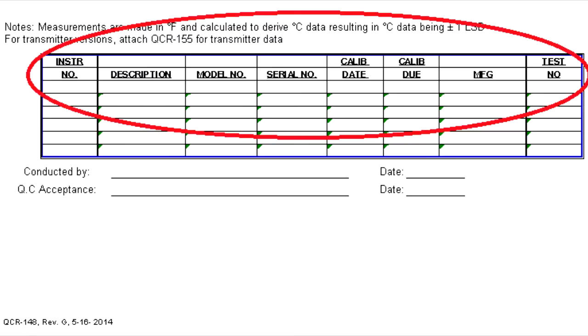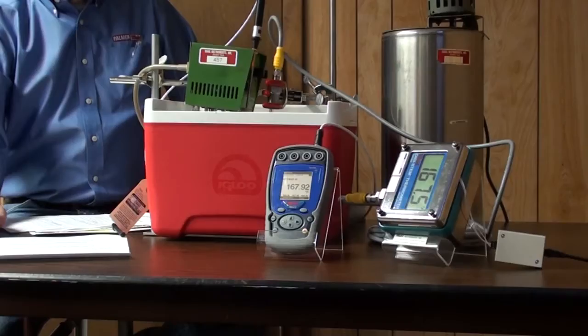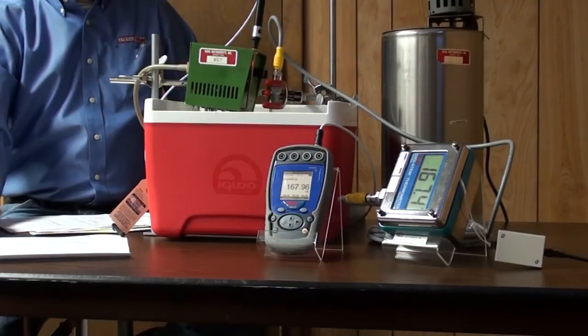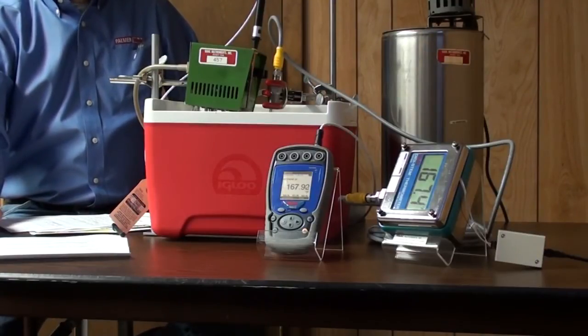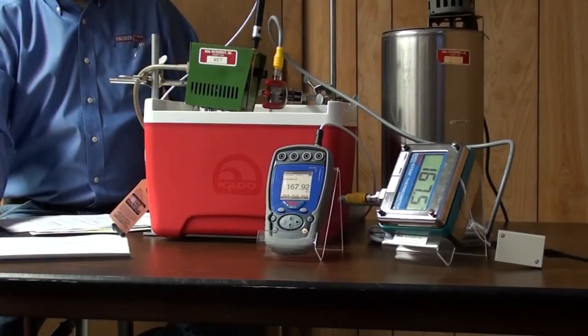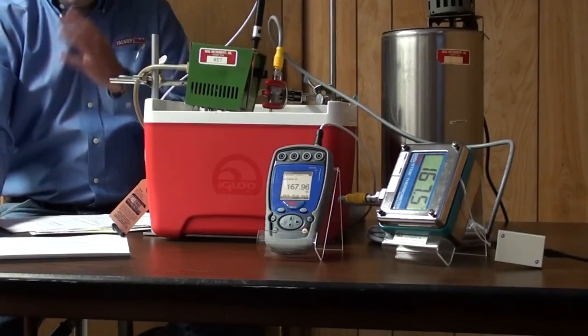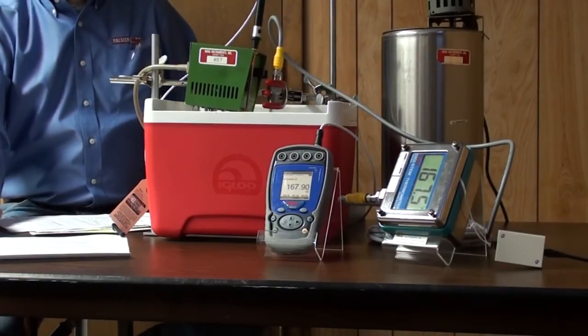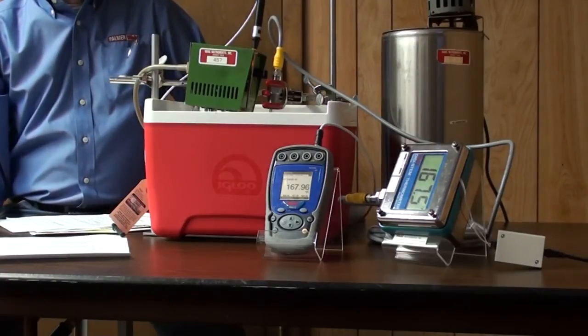Standard instrument description, that would go here. At a minimum, you would need a description of it. You should have some number assigned to that, although you could use model and serial numbers. Have the model number, serial number. Here's its calibration information, and here's the test report number. And then at the bottom is who conducted the test and QC acceptance. So this is a simplified one that was done in Excel, and we can go into the procedure now.